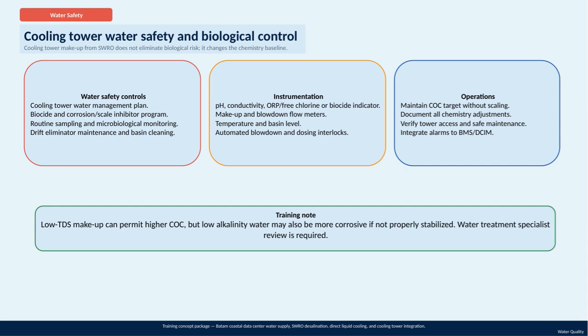Our training concept package uses data from the Batam Coastal Data Center's water supply, which includes SWRO desalination, direct liquid cooling, and how these integrate with the cooling tower. Understanding the water quality is fundamental for effective management. Key safety controls include a comprehensive cooling tower water management plan, combined with biocide treatments and corrosion or scale inhibitor programs. Routine sampling and microbiological monitoring are essential to keep the system safe, alongside regular maintenance of drift eliminators and basin cleaning to prevent contamination and buildup.